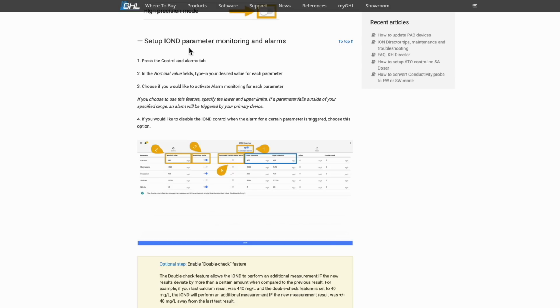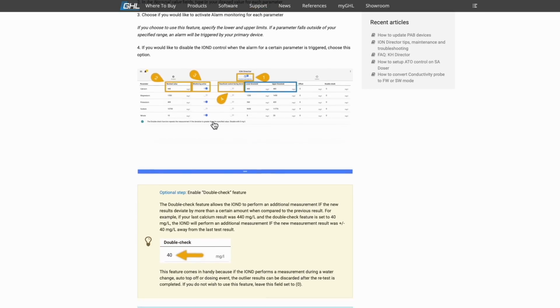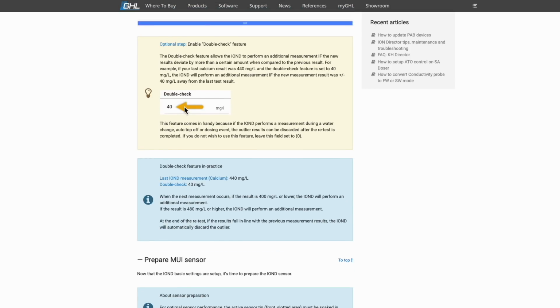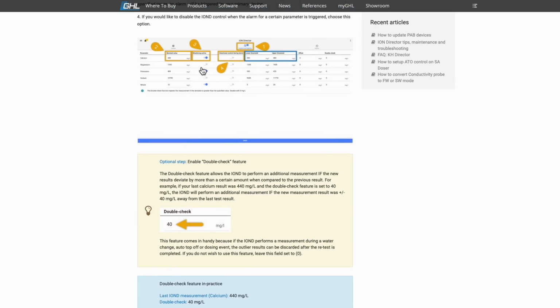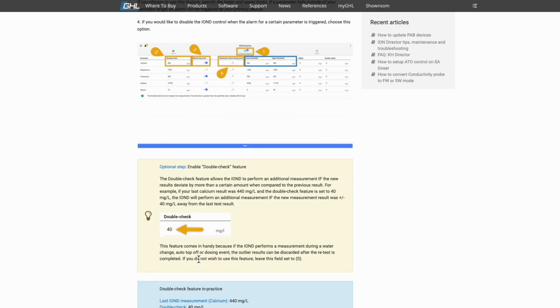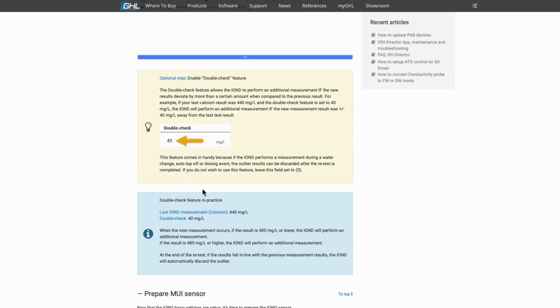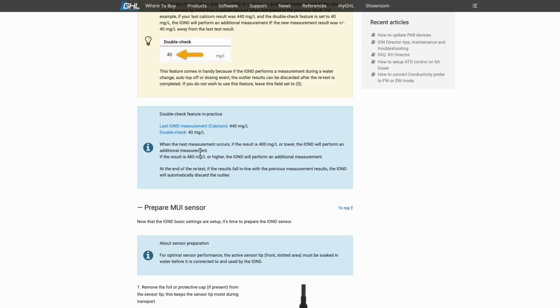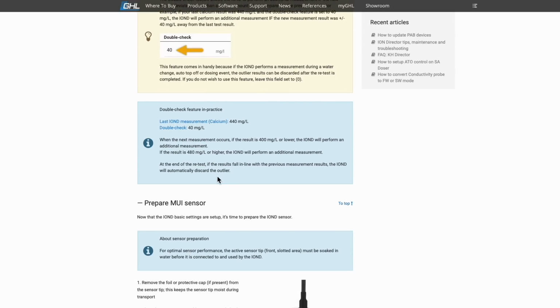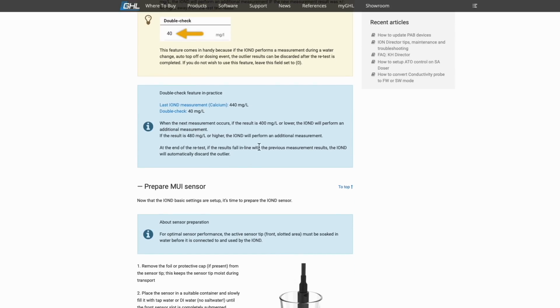Setup's not too bad. We've got to set up the Ion Director parameter monitoring and alarms, which is basically just picking a nominal value, and then how far outside of that range you want it to alarm. If you want to do a double check, which basically means how far it deviated from the previous test, do you want it to do another test to make sure?